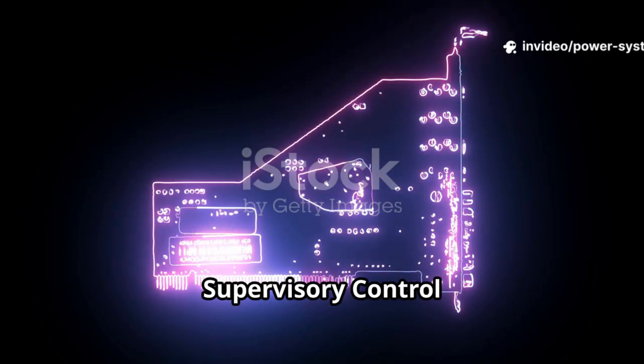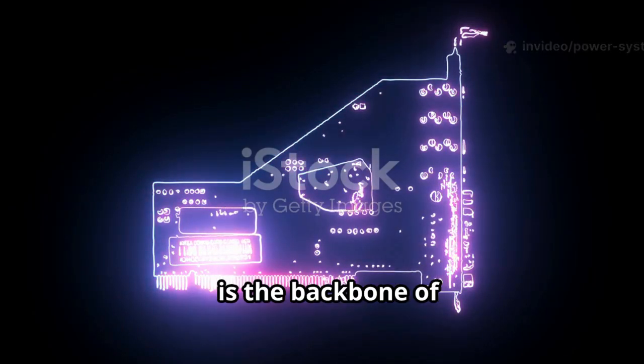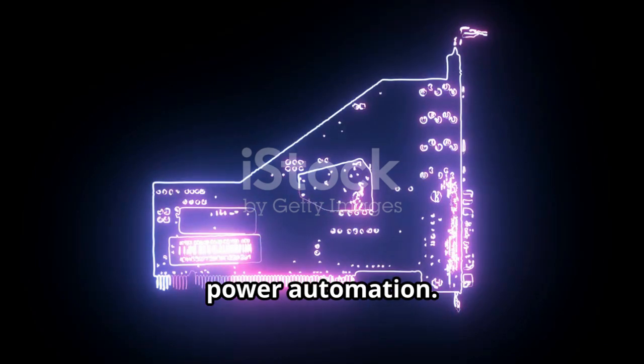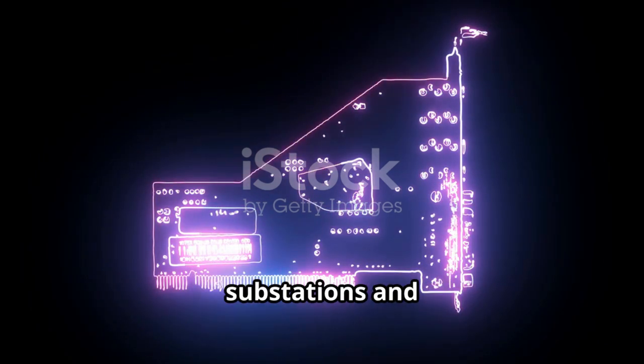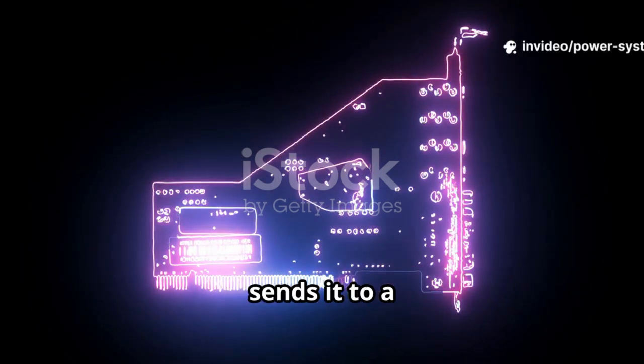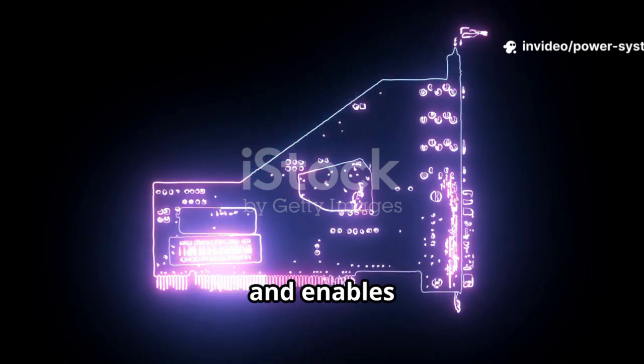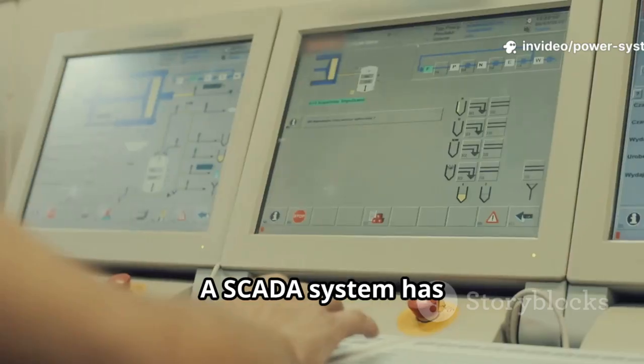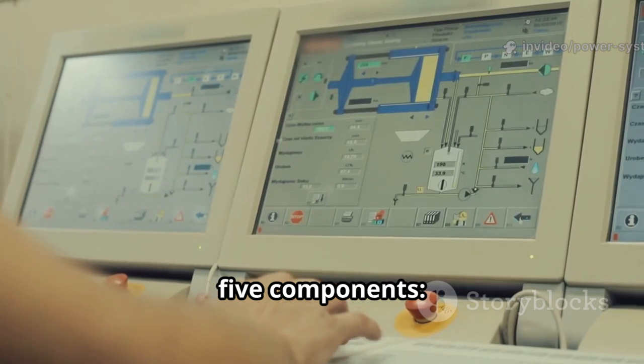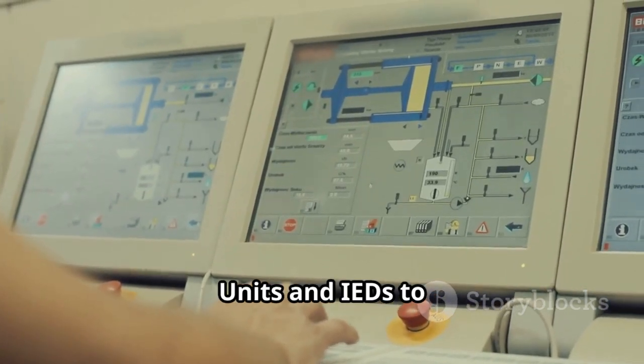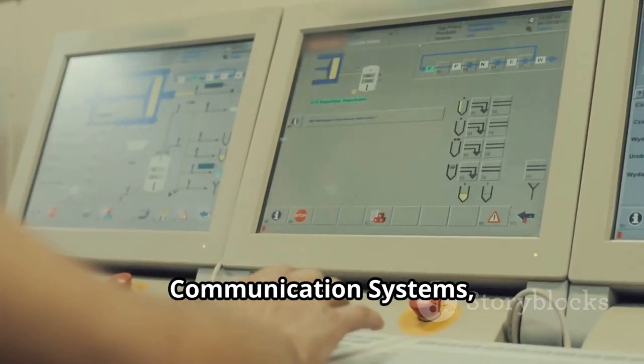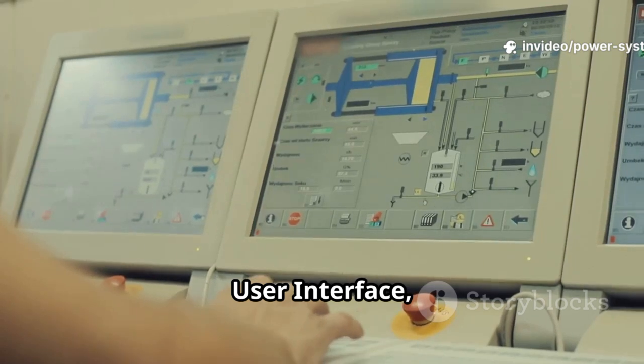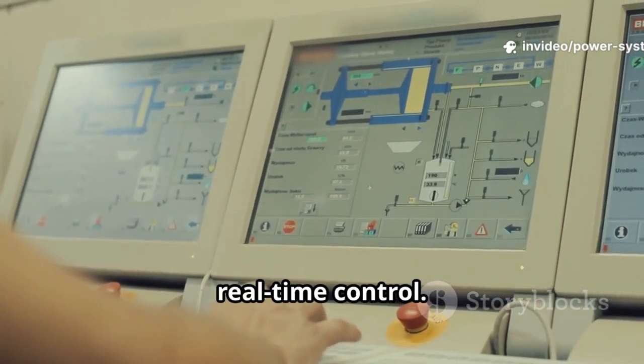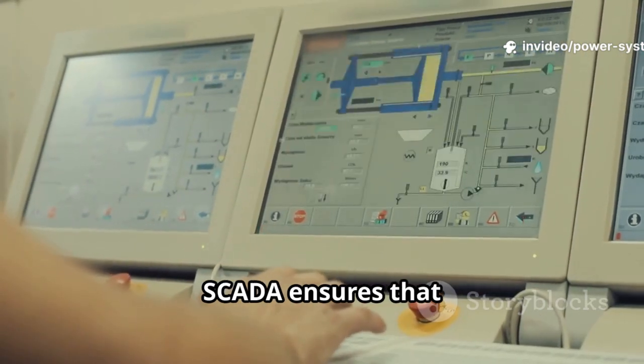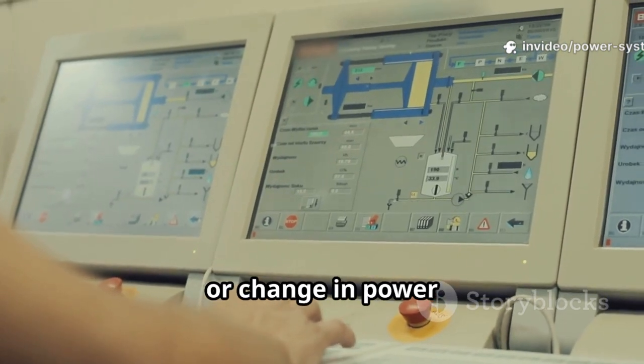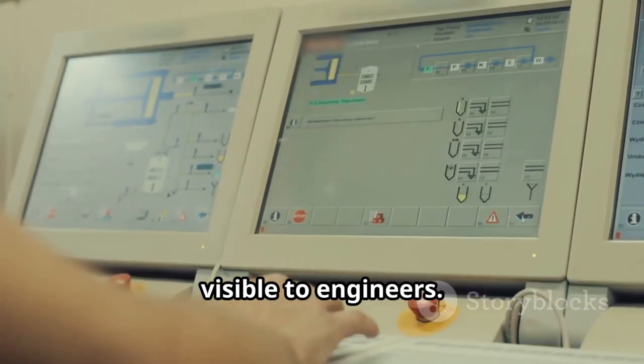SCADA, short for supervisory control and data acquisition, is the backbone of power automation. It collects data from sensors across substations and transmission lines, sends it to a central control room, and enables operators to take decisions. A SCADA system has 5 components: remote terminal units and IEDs to gather data, communication systems, master station and user interface, field instruments, and software for real-time control. SCADA ensures that every fault, alarm, or change in power flow is instantly visible to engineers.